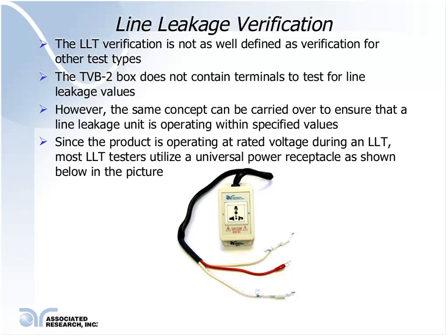We can use the TVB2 box, or something similar to it, but the TVB2 box that we have currently does not contain terminals to test for the line leakage values.